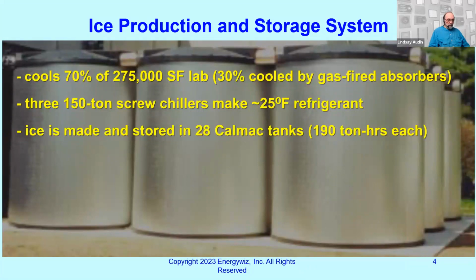The ice is made in that particular facility and stored in 28 CalMac tanks. If you want to read all about thermal storage, CalMac, C-A-L-M-A-C. These are the guys that have been doing it for 35, 40 years, whatever it is. Each of our storage tanks holds 190 ton hours. That's the rating of it. Actual amount you get is about 100, 110 ton hours.